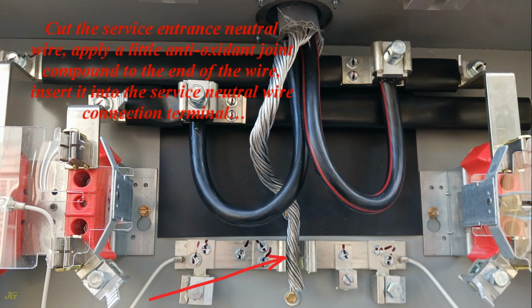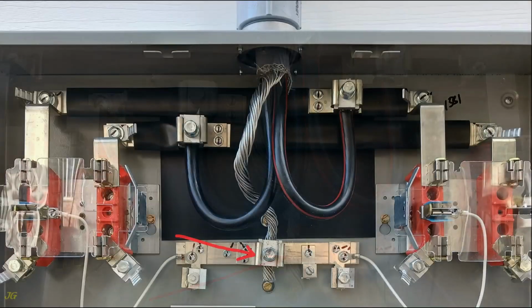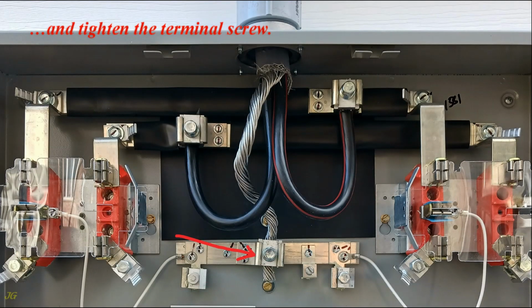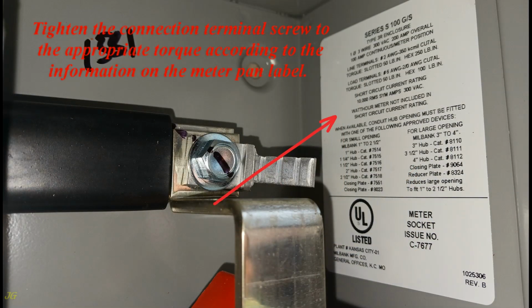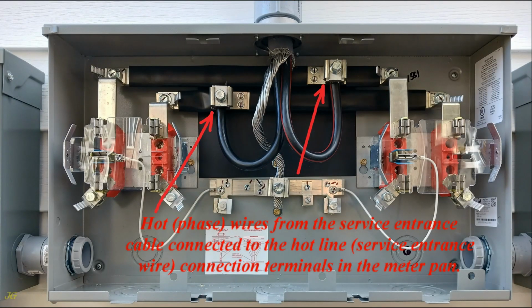Cut the service entrance neutral wire. Apply a little antioxidant joint compound to the end of the wire, insert it into the service neutral wire connection terminal, and tighten the terminal screw. Tighten the connection terminal screw to the appropriate torque according to the information on the meter pan label. Hot phase wires from the service entrance cable connected to the hot line, service entrance wire, connection terminals in the meter pan.